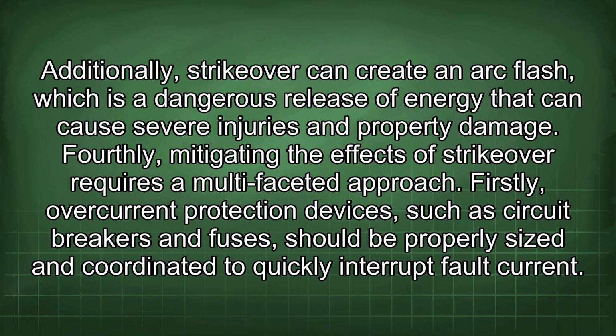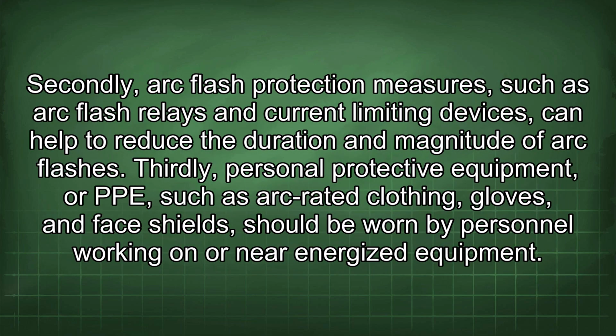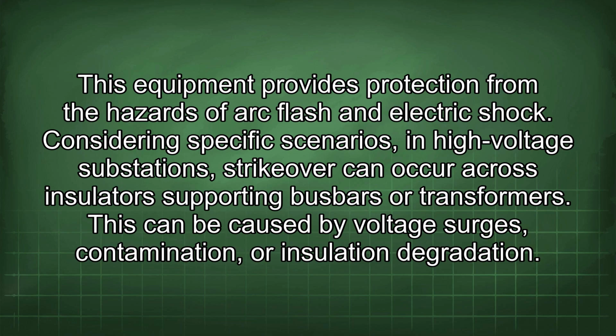Fourthly, mitigating the effects of strikeover requires a multifaceted approach. Firstly, overcurrent protection devices, such as circuit breakers and fuses, should be properly sized and coordinated to quickly interrupt fault current. Secondly, arc flash protection measures, such as arc flash relays and current limiting devices, can help to reduce the duration and magnitude of arc flashes. Thirdly, personal protective equipment, or PPE, such as arc-rated clothing, gloves, and face shields, should be worn by personnel working on or near energized equipment. This equipment provides protection from the hazards of arc flash and electric shock.